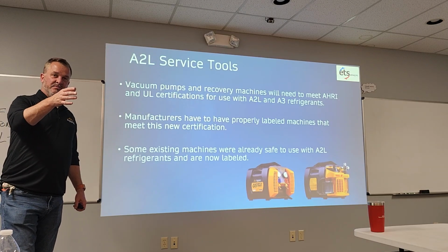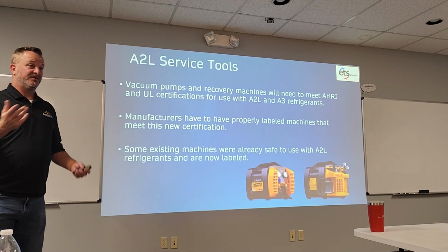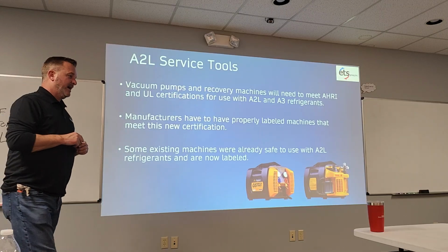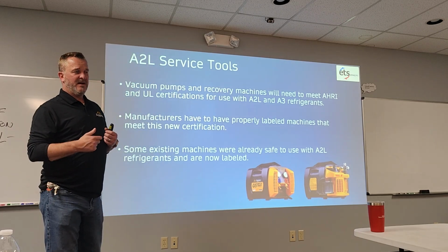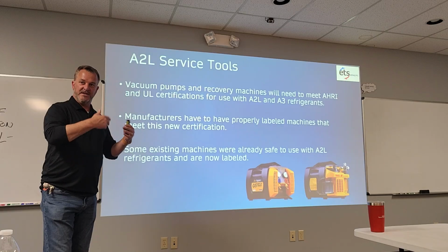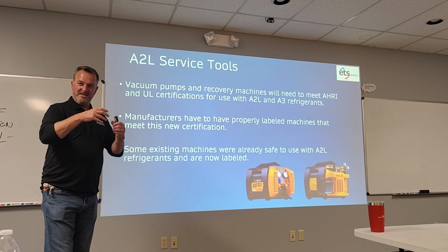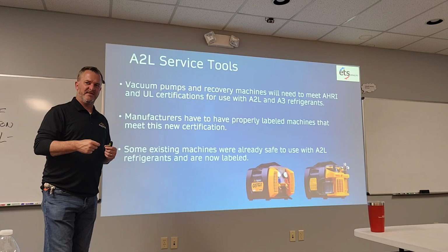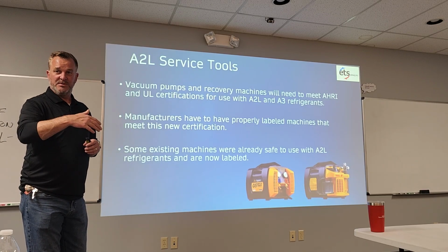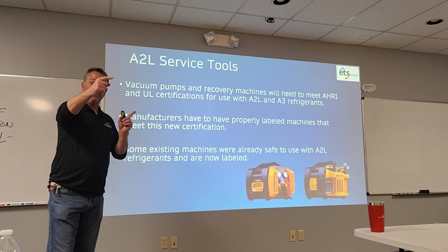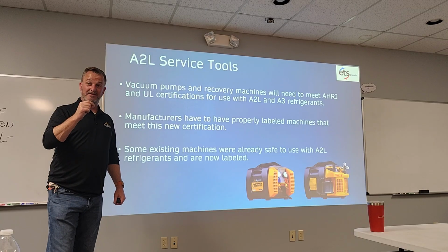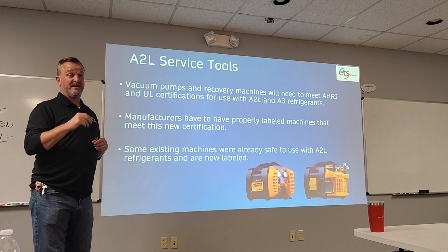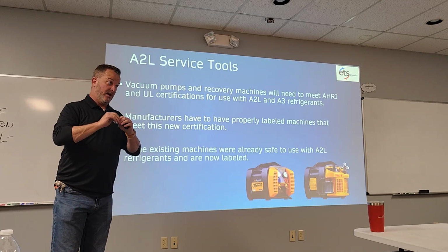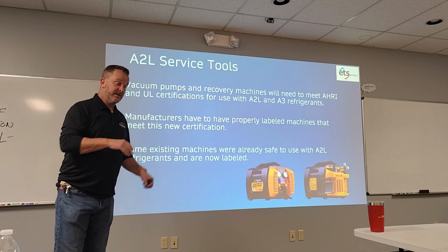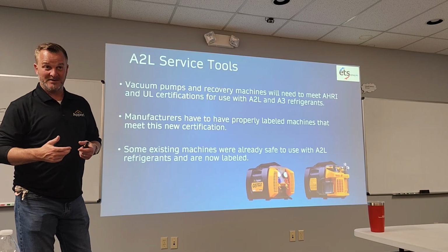Little story here: Appion is manufactured in Colorado Springs, Colorado, which was the first state to legalize a certain product. In manufacturing that product, they use a lot of butane. About 6-7 years ago, Appion, who do their own repairs, started finding resin and other residue when they took apart the piston housings. People were using these machines for grow houses to recapture butane. Butane would build up in the machine, and one little spark would cause an explosion. So the first thing Appion did was put out a liability notice saying they are not liable for any use with A3s, and that these machines are not to be used for A3 refrigerants. So again, do not recover A3 refrigerants, okay?